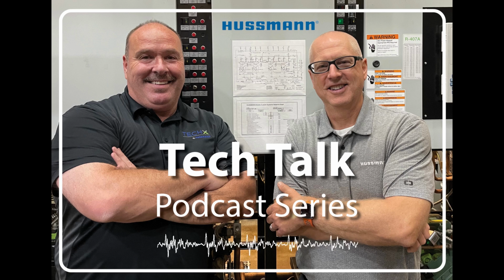Don, that is really good advice. So tell us a little bit more about the direct drive fan motors. Paul, condensers that use direct drive fans are a little more straightforward. Since the fan blade is mounted straight on the motor shaft, there's no other mechanical moving parts. The motor mounting cradle should be checked for cracks and vibration. Vibration is generally caused by a damaged fan blade or loose motor mounting.